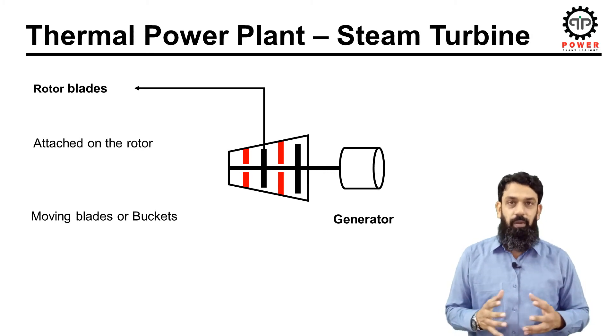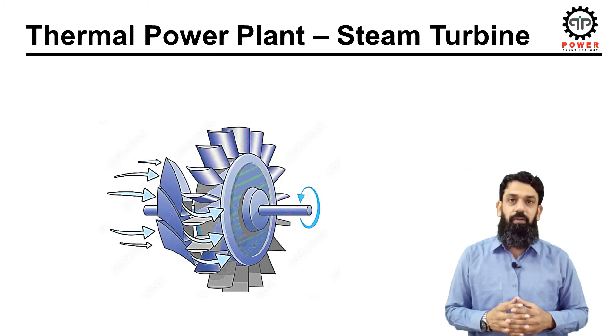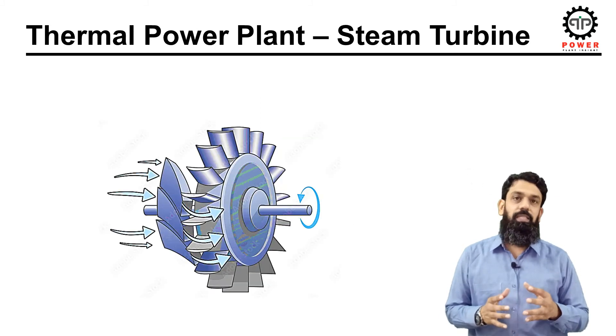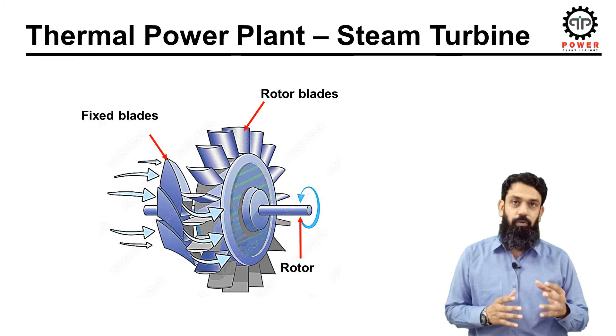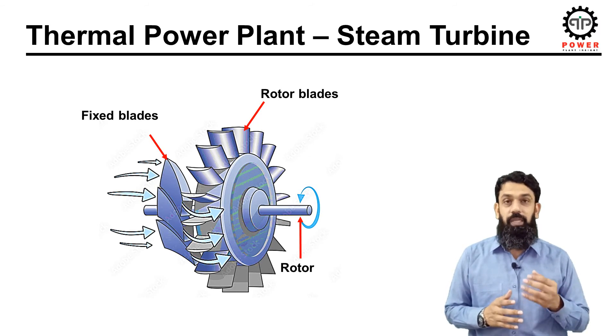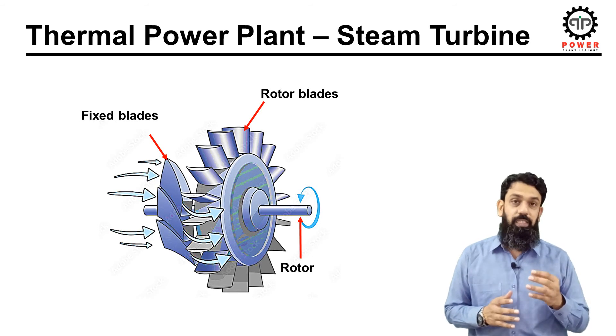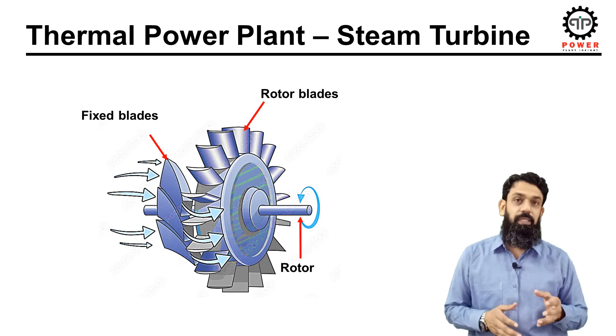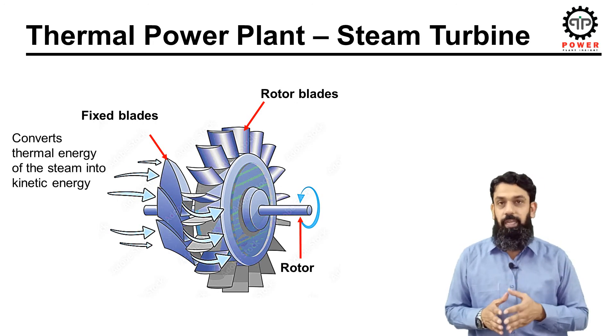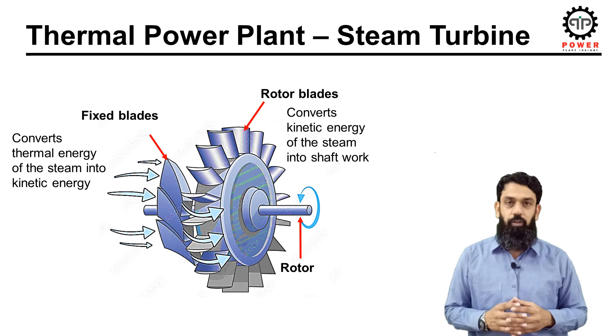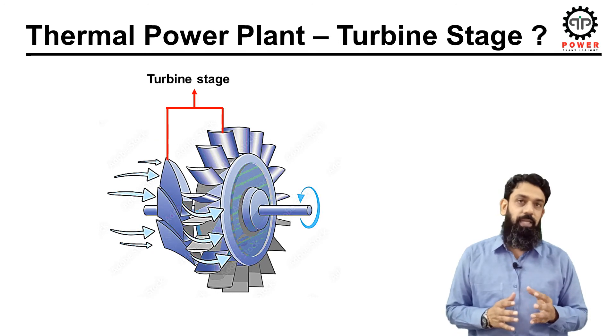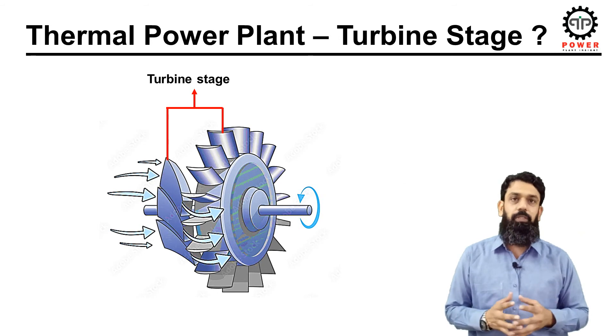Now let's discuss how the thermal energy of steam is converted into mechanical energy. These are fixed blades attached to the casing, and this is the rotor with rotor blades attached onto it. When steam leaves the fixed blades acting as nozzles, the kinetic energy or velocity of the steam increases and the steam changes direction towards the face of the rotor blades — this converts thermal energy into kinetic energy. The rotor blades then convert this kinetic energy into shaft work, resulting in rotational movement of the rotor, which is coupled with the generator to generate electricity. A set of fixed and rotor blades is called a turbine stage, and turbines usually have multiple stages depending on system requirements.